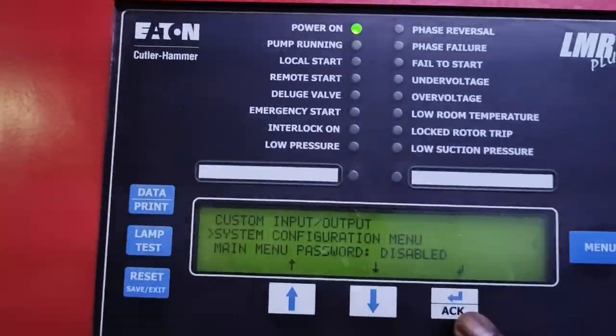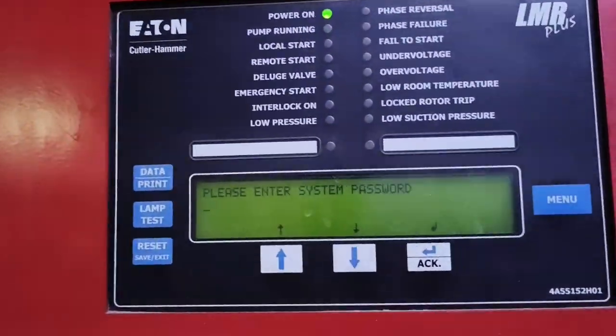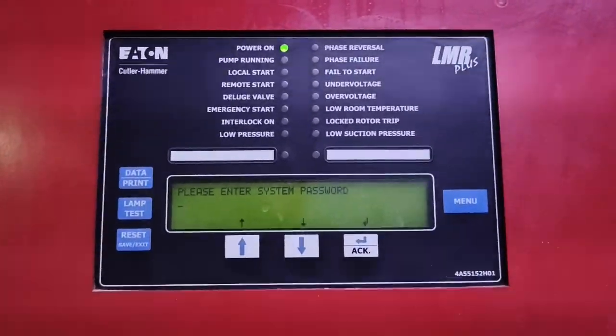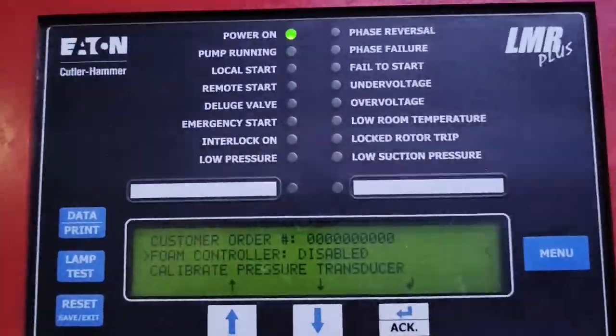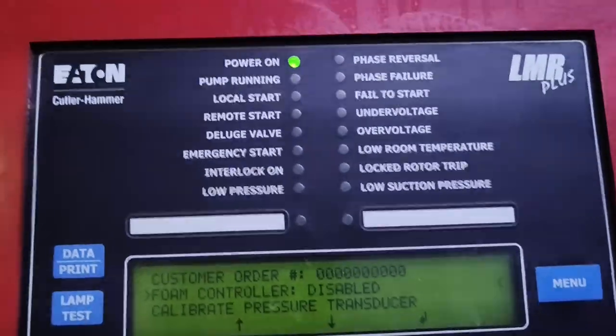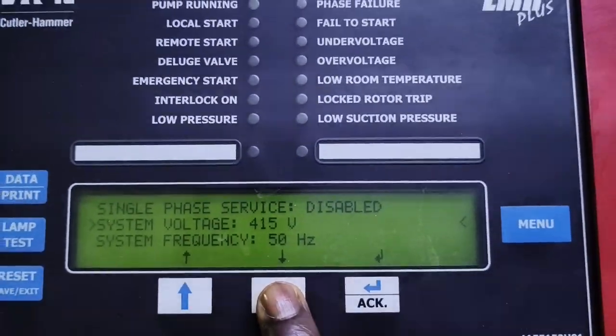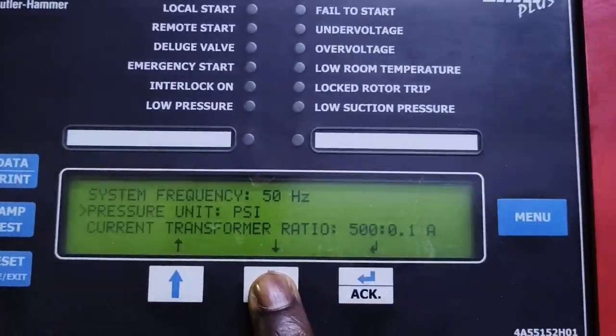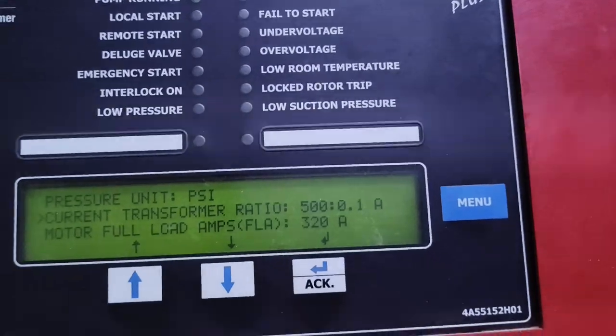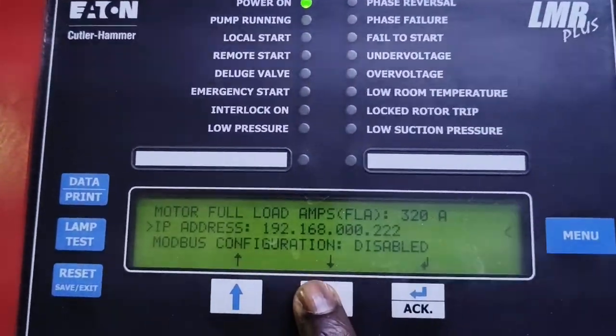System configuration requires a password. It covers a lot, including calibrations and more. Once you enter the password you have customer order, foam controller — disabled — calibrate pressure transducer, single phase service — disabled, system voltage at 415 V, system frequency, pressure units which you can change to bar or PSI, current transformer ratio of 500 to 0.1 amps, and motor full load amps at 320. You can check the motor's full load amps and enter it here.